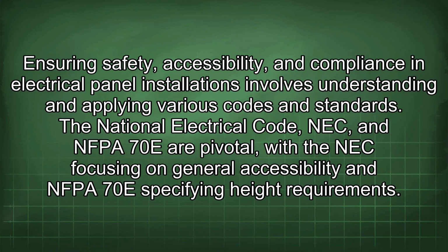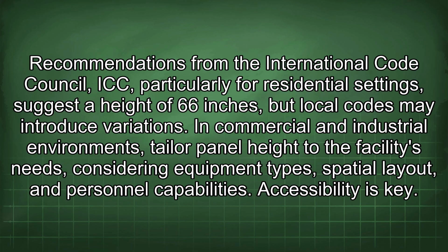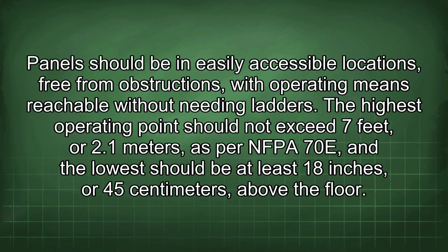specifying height requirements. Recommendations from the International Code Council, ICC, particularly for residential settings, suggest a height of 66 inches, but local codes may introduce variations. In commercial and industrial environments, tailor panel height to the facility's needs, considering equipment types, spatial layout, and personnel capabilities. Accessibility is key. Panels should be in easily accessible locations, free from obstructions, with operating means reachable without needing ladders. The highest operating point should not exceed 7 feet, or 2.1 meters, as per NFPA 70E, and the lowest should be at least 18 inches, or 45 centimeters, above the floor.